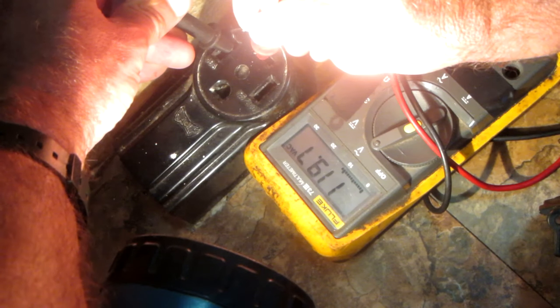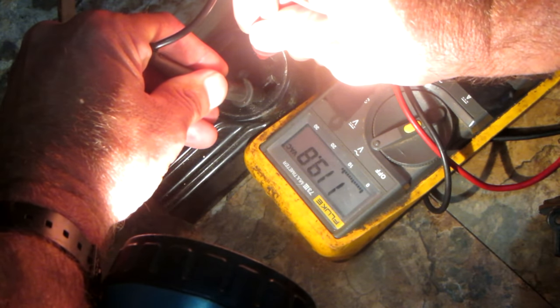Now I'm going to put my lead in the neutral hole. On one side I read 119.7, and the other side I read 119.8. So far everything on this is checking out exactly the way it's supposed to.